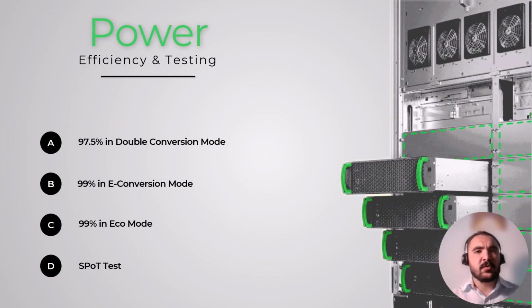Efficiency and testing. We've come to one of the most exciting slides in this presentation. The Galaxy VXL UPS delivers the highest level of efficiency compared to all of the UPS in the range of Schneider Electric. It provides an efficiency of 97.5 in double conversion mode, 99% in eco mode, and 99% in e-conversion mode. Additionally, the UPS includes a spot test to check the UPS status under different loads.